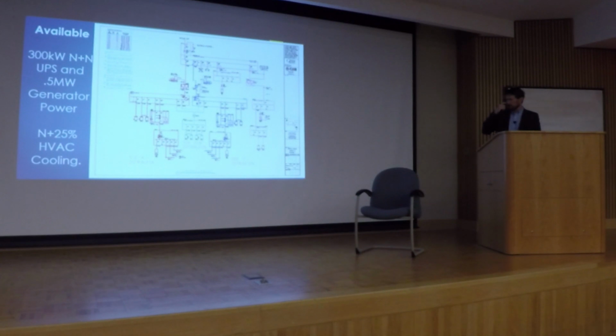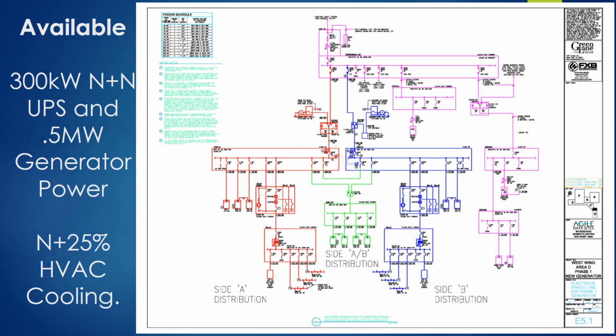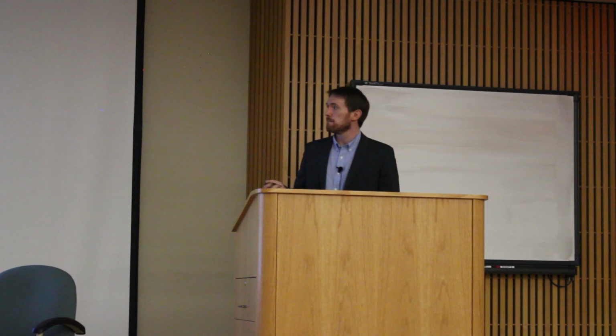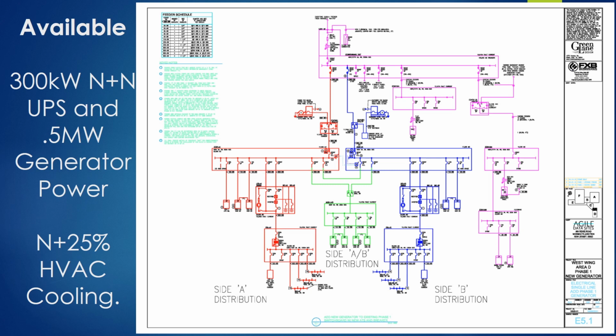This goes into what the architecture looks like and how we get that availability. You can see there's a red side and a blue side, and in the middle is green. The red side is the A side, the blue side is the B side, and the section in the middle is fed from both A and B. So if the A side goes down, we still have 100% of the electrical systems and 90% of the HVAC systems. If the B side goes down, same thing.